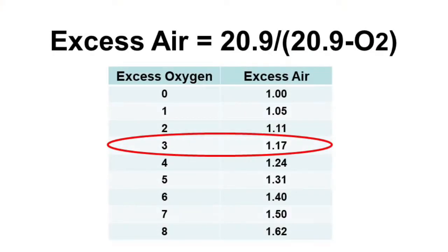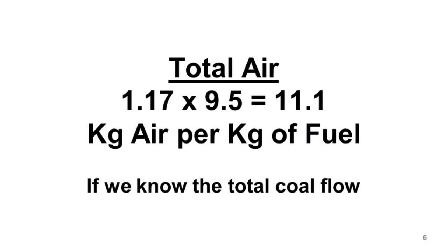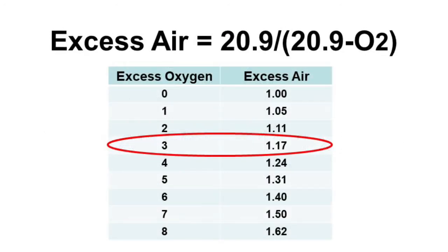We actually found an expansion joint failure with a big tear on the side where the oxygen probe read high. Can you show me how you got to that conclusion? Let me show you the airflow calculations I used. The low airflow values calculated out to a true excess oxygen value of only about one percent — typically you try to run three. This created a high CO environment because the furnace oxygen was only about one percent. That's what happened when that O2 gauge started reading high numbers like eight or nine.